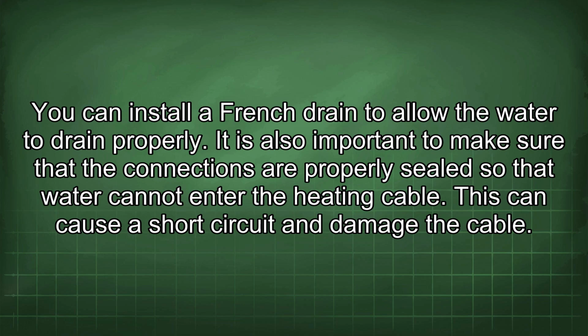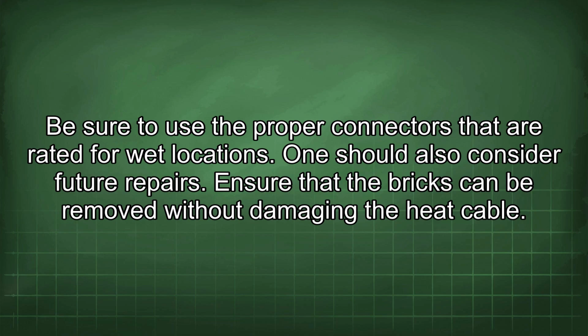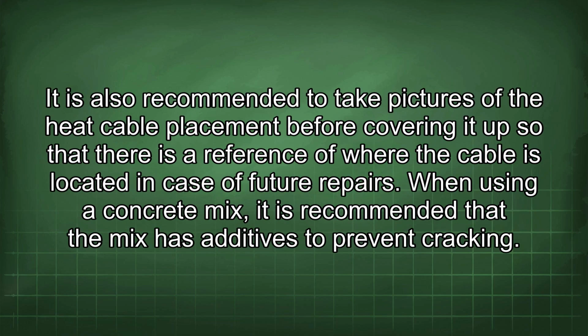It is also important to make sure that the connections are properly sealed so that water cannot enter the heating cable. This can cause a short circuit and damage the cable. Be sure to use the proper connectors that are rated for wet locations. One should also consider future repairs. Ensure that the bricks can be removed without damaging the heat cable. It is also recommended to take pictures of the heat cable placement before covering it up so that there is a reference of where the cable is located in case of future repairs.